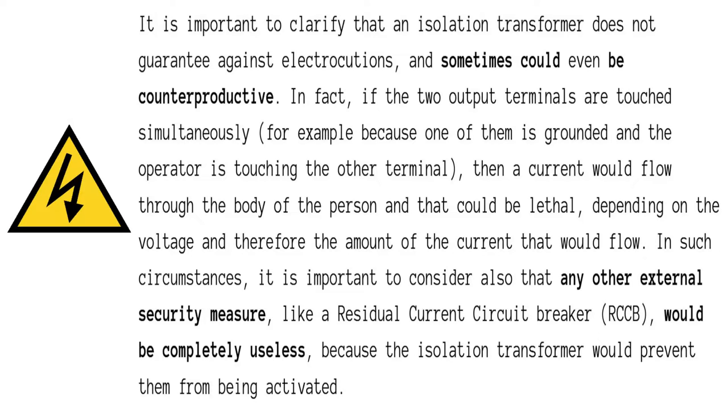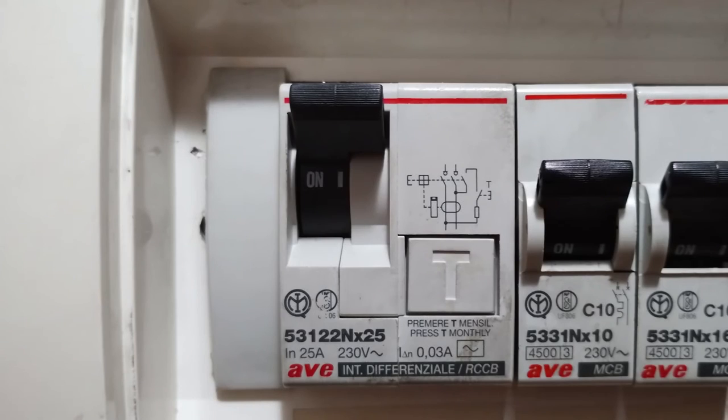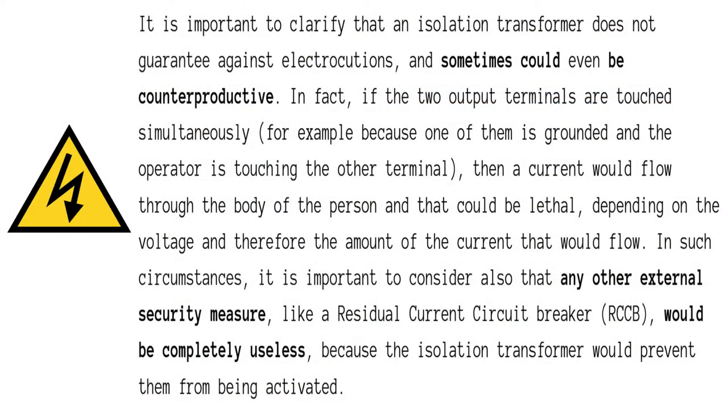In such circumstances, it is important to consider also that any other external security measure, like a residual current circuit breaker, would be completely useless because the isolation transformer would prevent them from being activated.